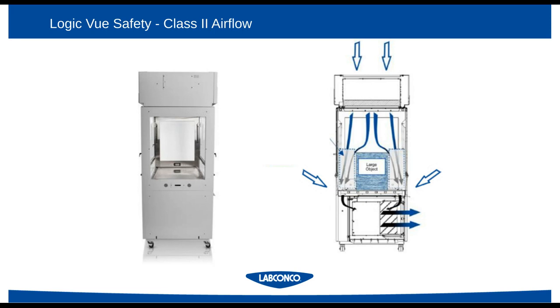And to keep users safe, it keeps a minimum inflow of 105 feet per minute, just like a Class II biosafety cabinet. The air is also exhausted through the lower portion of the enclosure, and it goes back into the laboratory, or can be vented, especially if you're using something that has an unpleasant smell or is perhaps warranting the use of exhaust for a different reason.